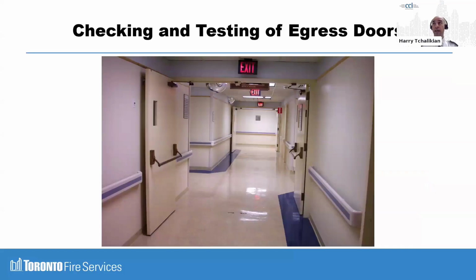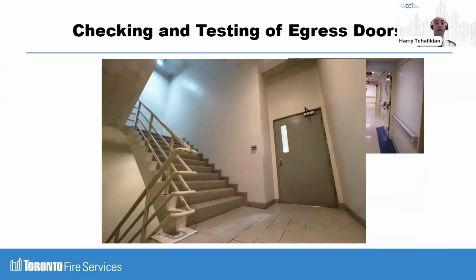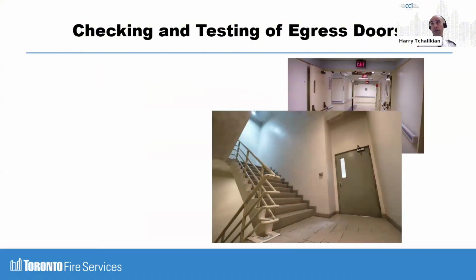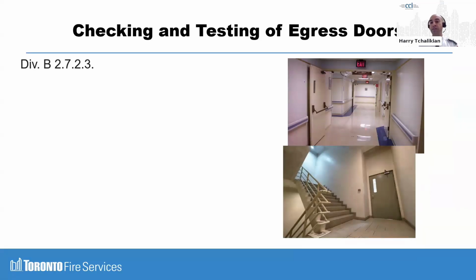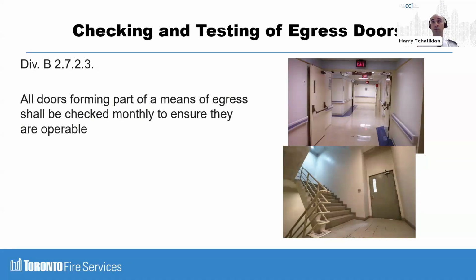Next requirement, checking and testing of egress doors. Egress means simply leaving the building. An extension of that definition, the umbrella term, is means of egress. A means of egress is anywhere where you can possibly stand in the building, every door that's in your way. So now there's checking and testing of these egress doors to make sure that there's no door that would not function. This is new. So Division B 2723: all doors forming part of a means of egress shall be checked monthly to ensure that they are operable. Under the fire code, there are checks, inspections, and tests. You always need to keep test records. Whenever the fire code says a test is required, those records need to be kept in full. Anytime something is a check or an inspection, you only need to keep a record if you're prompted on a case-by-case basis. In this case, there's no requirement to keep records of this check.